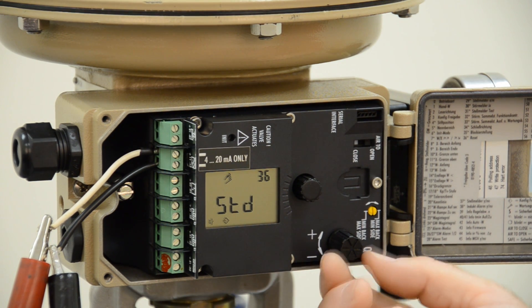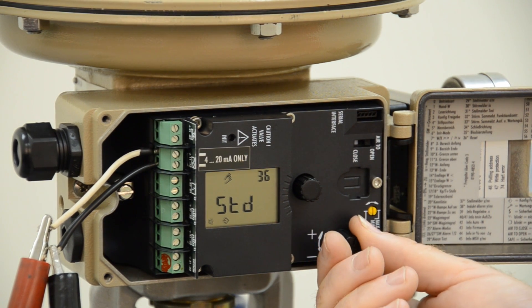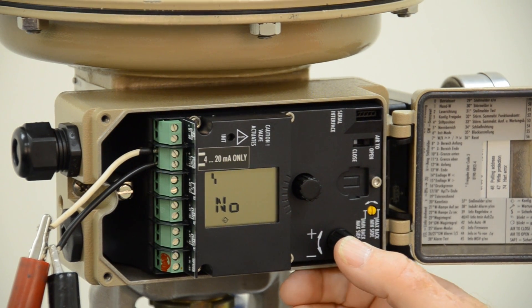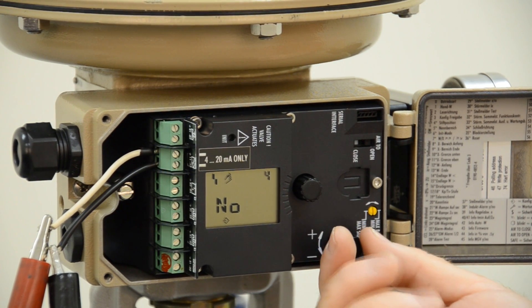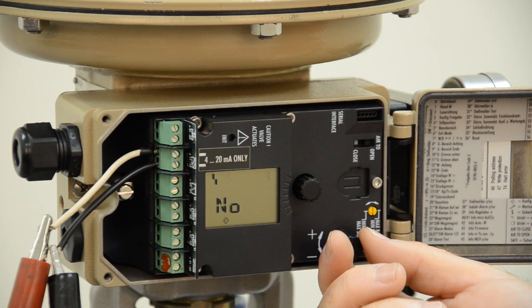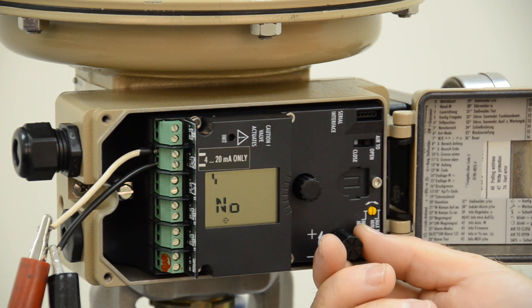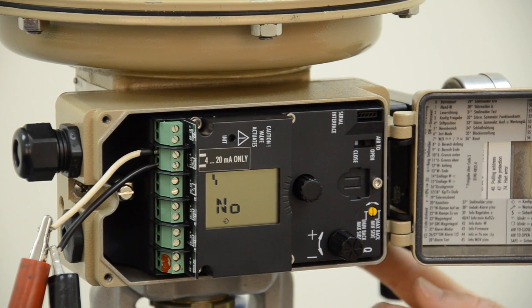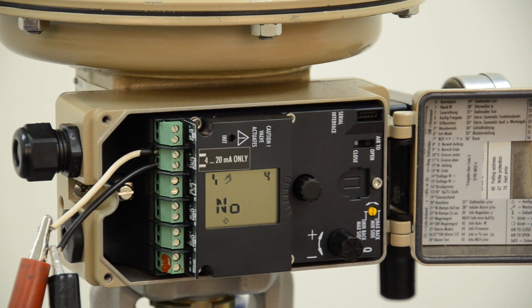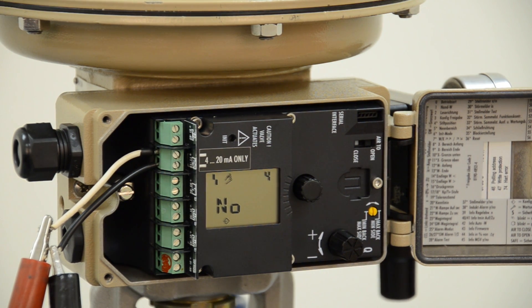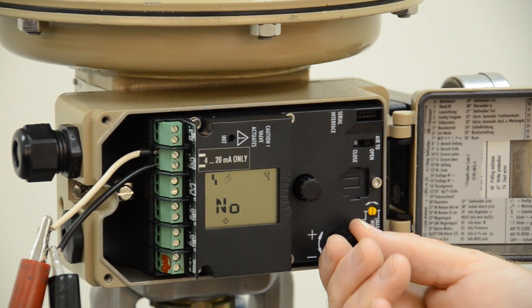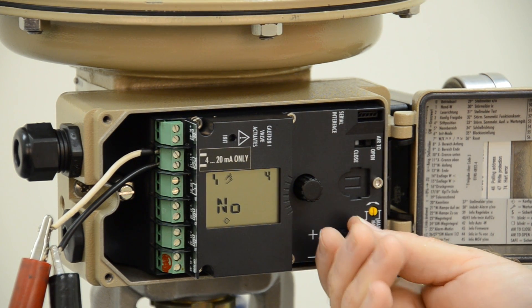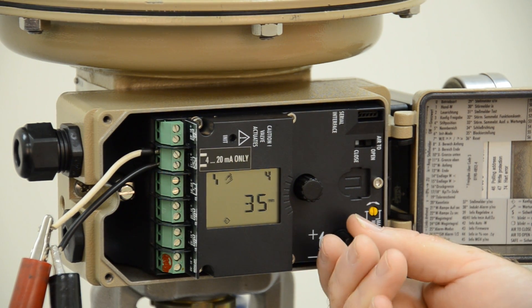Our next code will be code 4. Once we get to code 4, we press. This is going to be the setting for the positioner arm located on the back of the positioner. And depending on the type of valve, it's where the pin goes to match the valve stroke that you need. In this case, we're instructed to go to pin position 35.